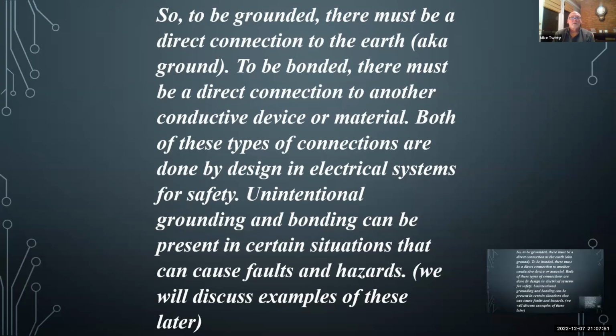Okay, so to be grounded, there's got to be a direct connection to the earth. To be bonded, there must be a direct connection to another conductive device or material. Both of these connections are done by design, and unintentional grounding and bonding can be present in certain situations that cause faults and hazards. We're going to look at some of those in a minute.